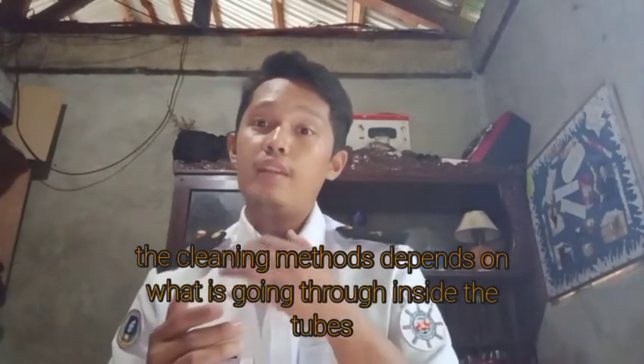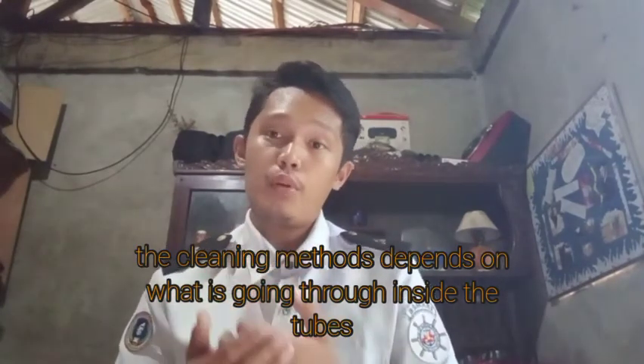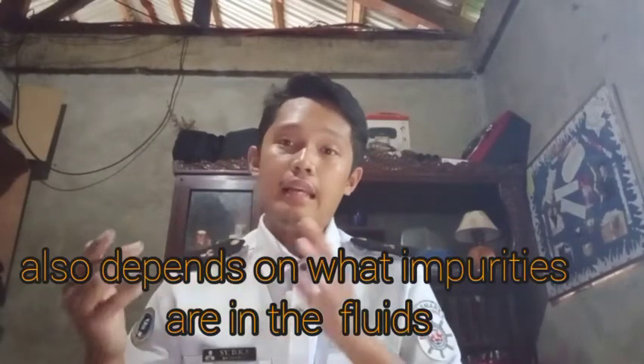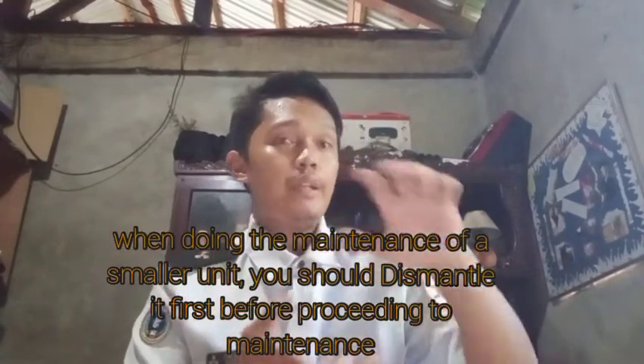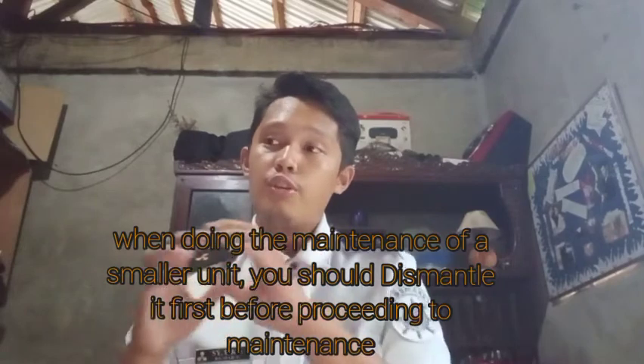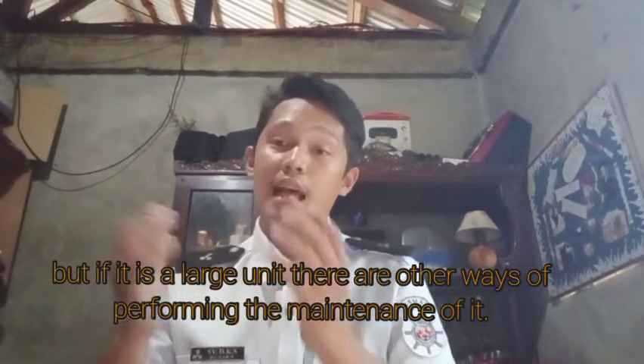The cleaning methods depend on what is going into the heat exchanger, and also on what impurities are in the fluids. So there are many styles of cleaning the tubes in a tube type heat exchanger. When you are maintaining a smaller unit, it is advisable to dismantle it before cleaning or doing maintenance work, so that it is ready to use. But if it is a large unit, there are many styles of cleaning the tube type heat exchanger.